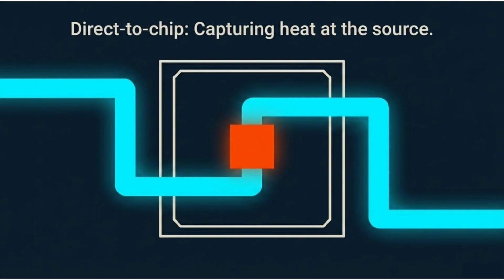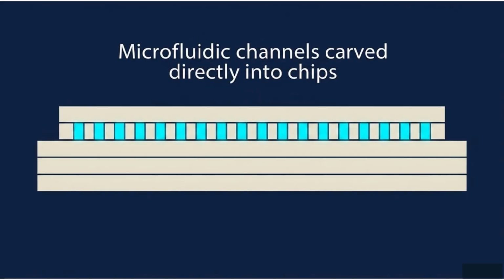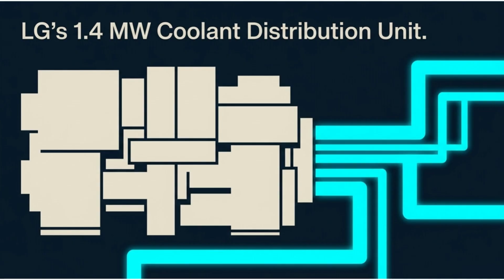The first step is called direct-to-chip cooling. Instead of blowing air around the whole room, we pump cold liquid through tiny metal pipes that rest directly on top of the silicon chips. Engineers are even getting microscopic with it. They're actually carving tiny, microfluidic channels right into the chips themselves, so the cooling liquid flows directly through the hardware's veins. To handle all this high-tech plumbing at scale, companies are building massive coolant distribution units. LG's newest system can manage 1.4 megawatts of heat in a single setup.